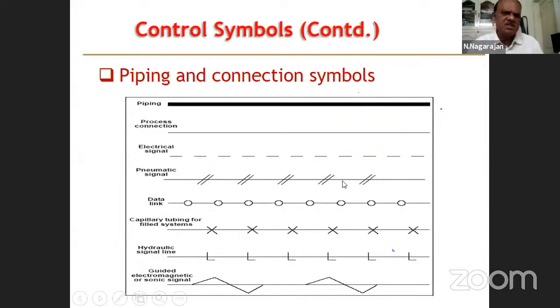And there are a lot of signals we use in the piping and instrumentation diagram. The process pipe is shown like this, process connection. Electrical signal is a dotted line. Pneumatic signal, that is a pressure. Instrument air is being used for opening or closing of the valves. So this is the horizontal line with two hatches at uniform interval. This is the pneumatic signal. Data link is something to do with the computer configured variable. This is called data link, serial data link.